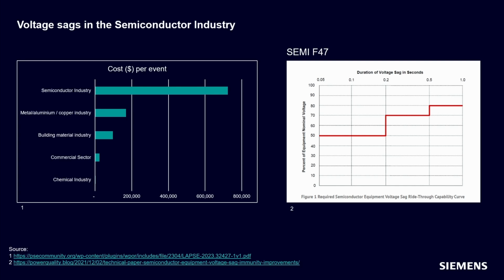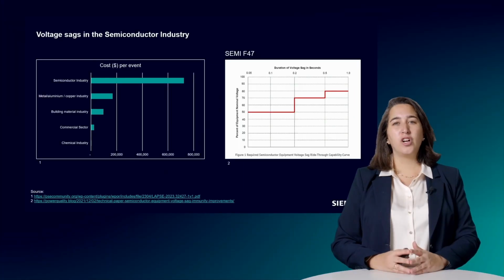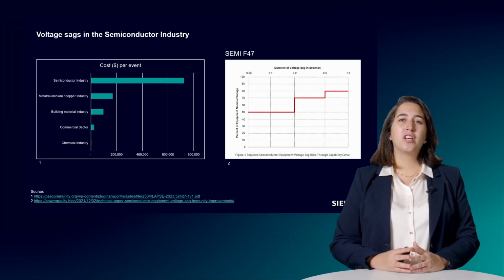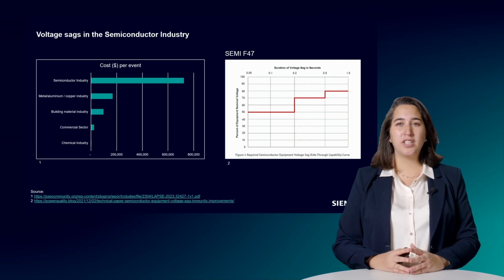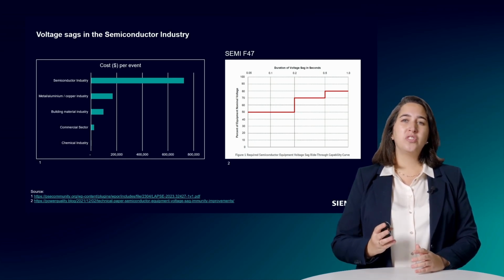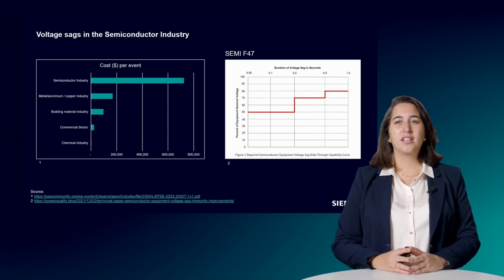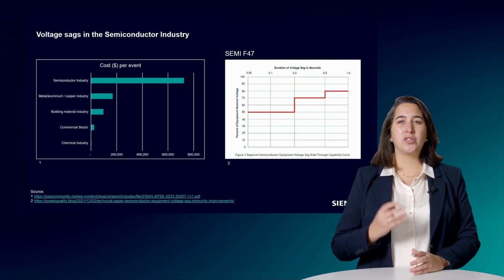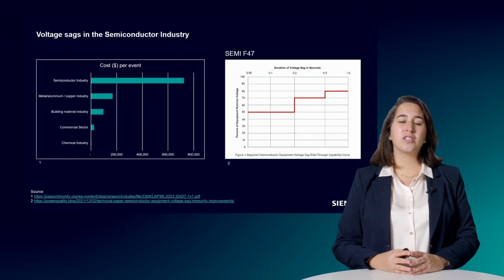Semiconductor facilities rely on a high level of power availability and quality due to the sensitivity of specialized manufacturing equipment and precision of process controls in the wafer fabrication. Voltage sags or voltage dips, the most common types of power quality issues experienced in the semiconductor industry, cause loads to de-energize.